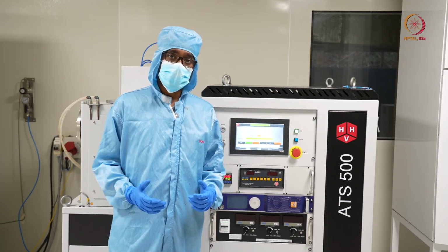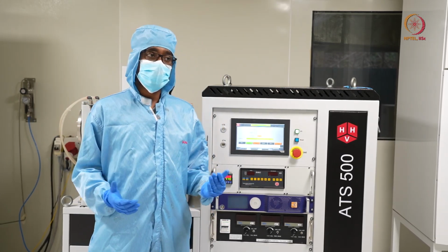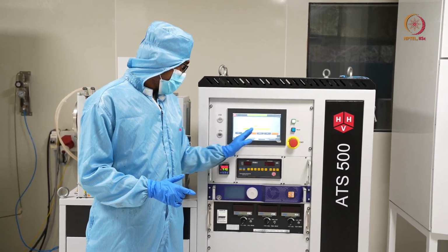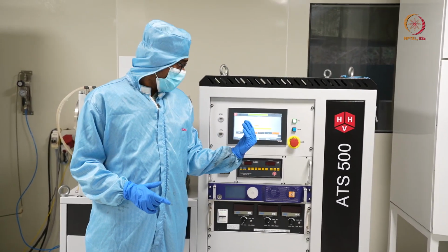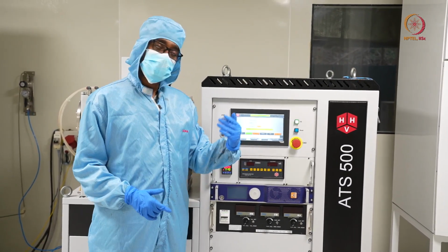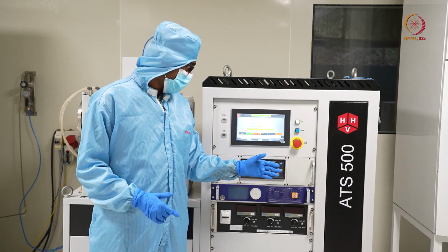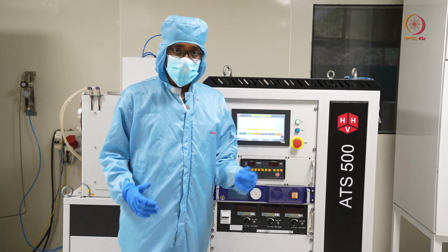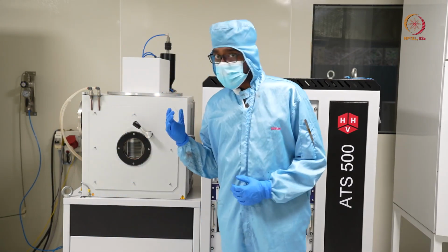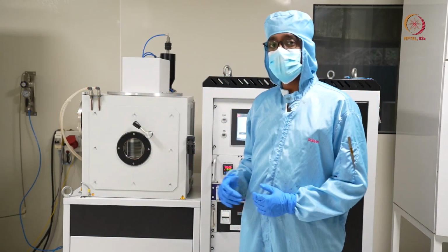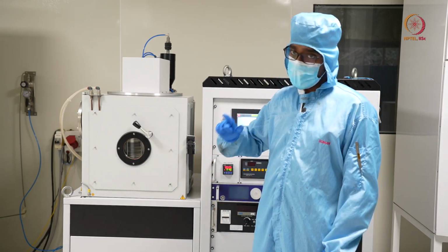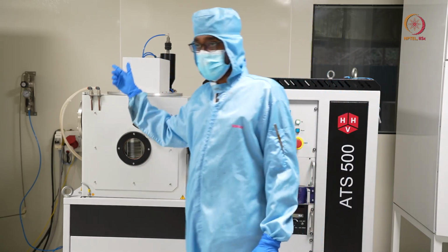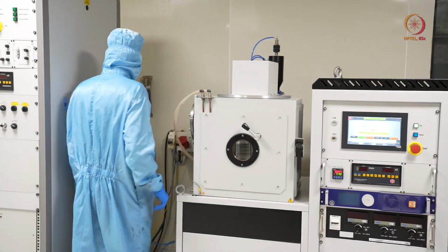We are not pressing start this time, because as we have shown when we started the tool, we had to start the tool so that the pumps will be on, after that we go for a cycle. So this is not the case this time. Another thing is, we are about to turn off the tool, so we know that we are not going for further deposition. So mandatorily we have to switch off the gas supply. That we will do first.